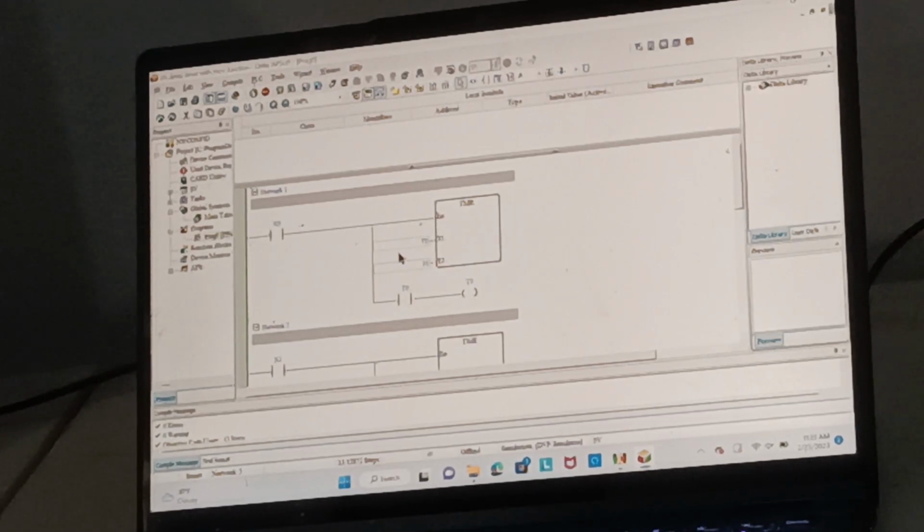Right, if you were to get a printout of what's going on in the PLC that this is programmed in, you would notice we have a timer, TMR, and this timer is T0 right there. So that's timer 0, and it is set to 30. Well, what's 30? Well, in Delta, this is 1/10 of a second, so this is really 3 seconds. So you'd want to know what that value stands for. But basically, this is a 3-second timer.